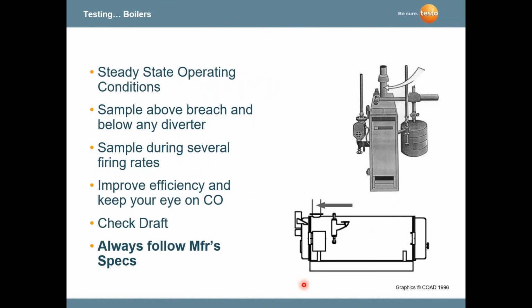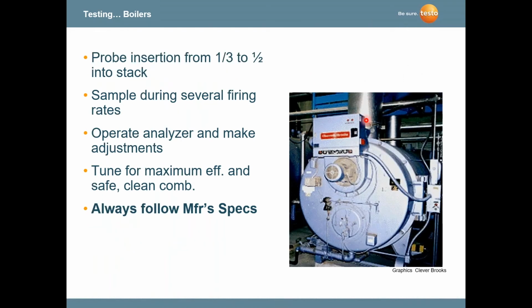Now, as far as boilers itself, getting into larger boilers, in sampling, your probe tube has to be below any type of draft diverter, right above the breech of a boiler so you can pull in the flue gases. So there's no dilution. If you're above that draft diverter, you can get a lot of dilution here, causes readings to be exaggerated a little bit. Usually a 1/3 to 1/2 penetration into the stack. There are probes out there that we have that are much longer than the standard length, which is roughly 1/2 meter or so. Sampled during the different fire rates. The key is to tune the maximum efficiency and make sure that your carbon monoxide is low, and follow the manufacturer's specification.